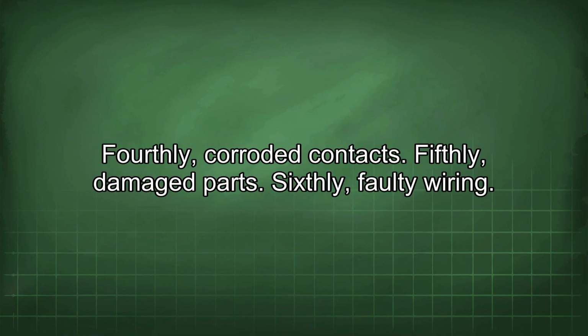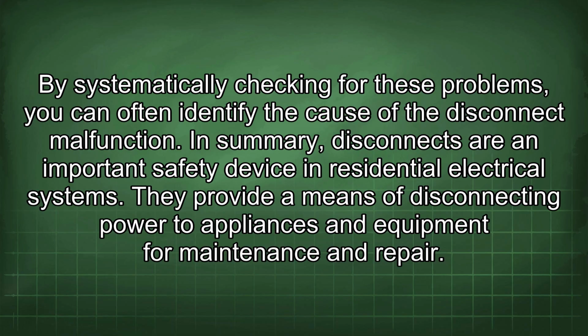Fourthly, corroded contacts. Fifthly, damaged parts. Sixthly, faulty wiring. By systematically checking for these problems, you can often identify the cause of the disconnect malfunction. In summary, disconnects are an important safety device in residential electrical systems. They provide a means of disconnecting power to appliances and equipment for maintenance and repair.